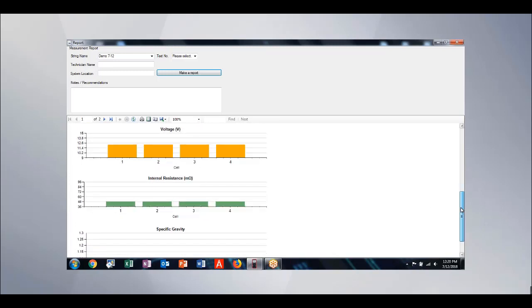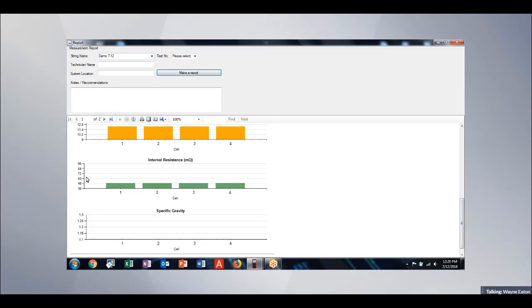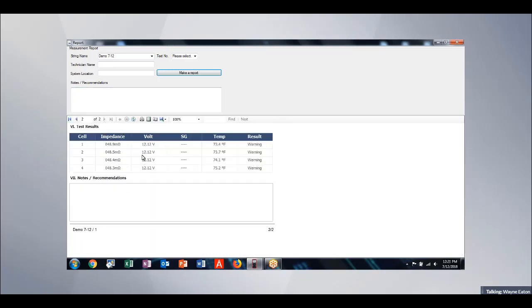If I was using the SBS-2003, I could import the specific gravity readings, and the specific gravity of those cells would show up in this report as well. On the second page and third page of the reports are actually the numerical data for each one of the measurements I've taken. So you can see here's my internal resistance, my voltages, my temperatures, and then the pass, warning, or fail result. This report can be printed directly from the software, or it can be saved to an Excel spreadsheet, a PDF file, or a Word document.